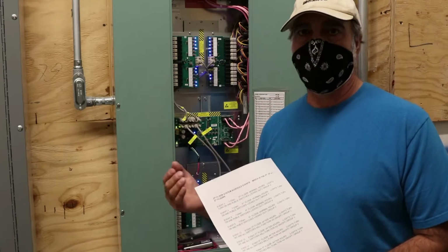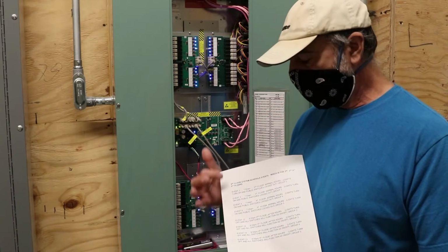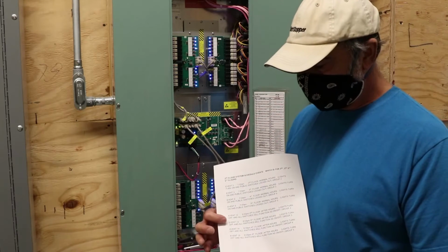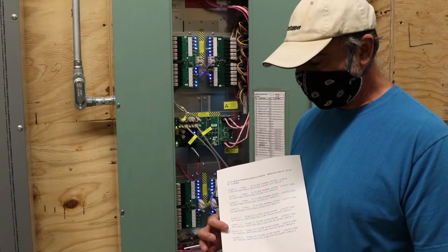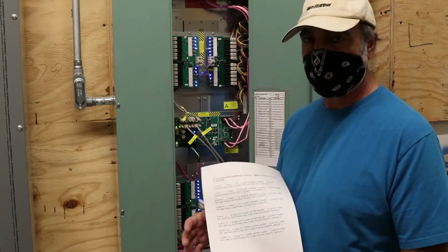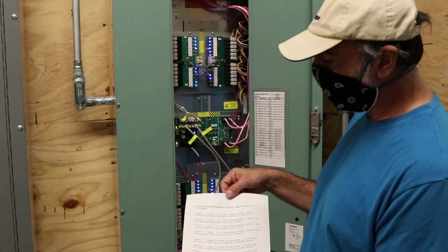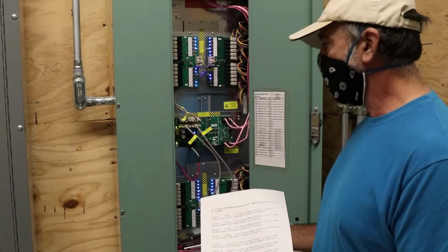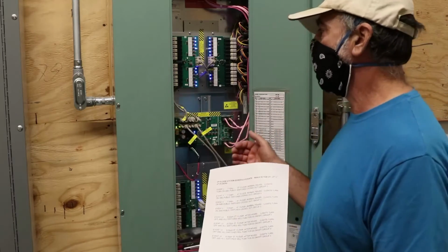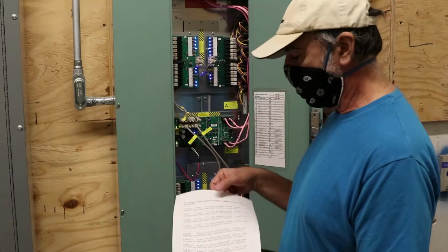You need another event to turn those lights off. So I made event 12 kind of in parallel with 2. That's floor 2 off. 13 is floor 3 off. 14 is 4 off. And 15 is 5 off. So this gives you the times I already put in there. And I did the floors separately in the event. Maybe the 5th floor isn't as occupied as other floors, and they may want to turn the lights off earlier or not turn them on at all. And that's why we're going through how to edit this.